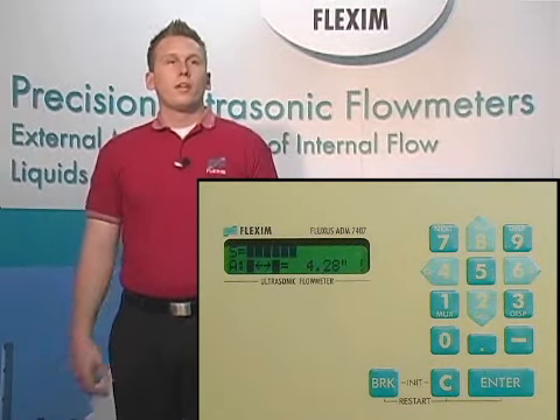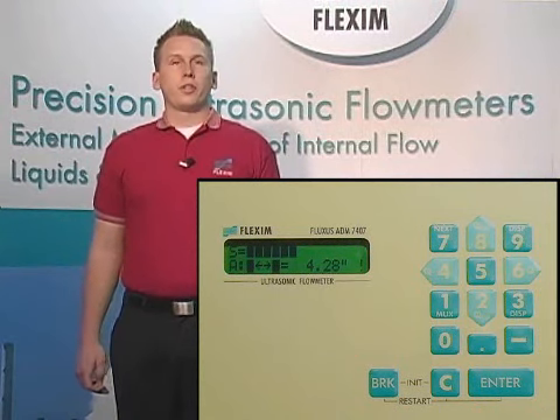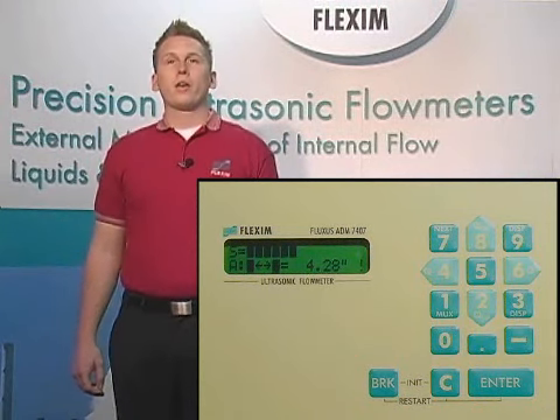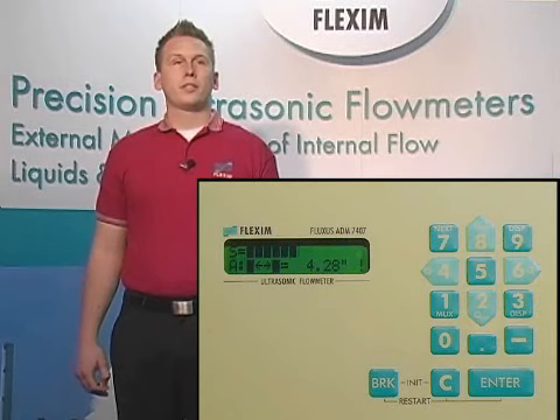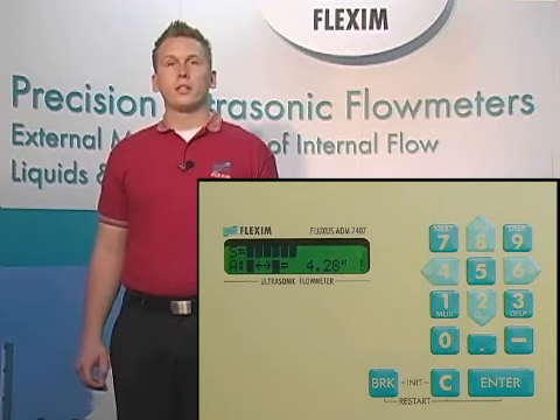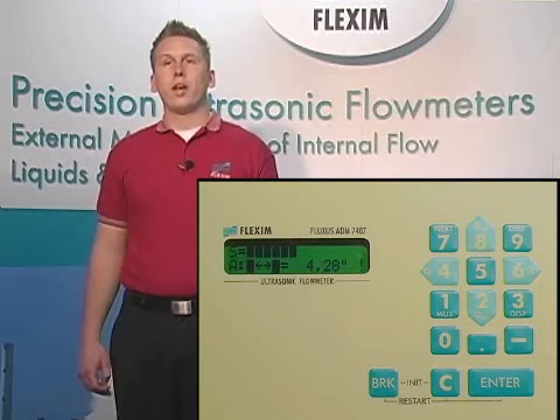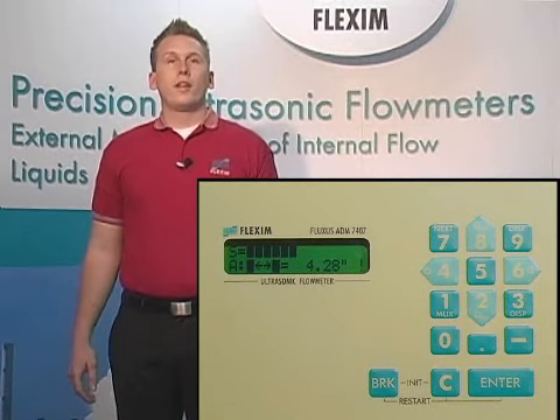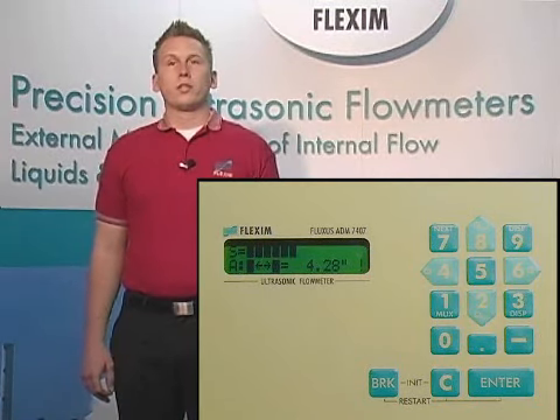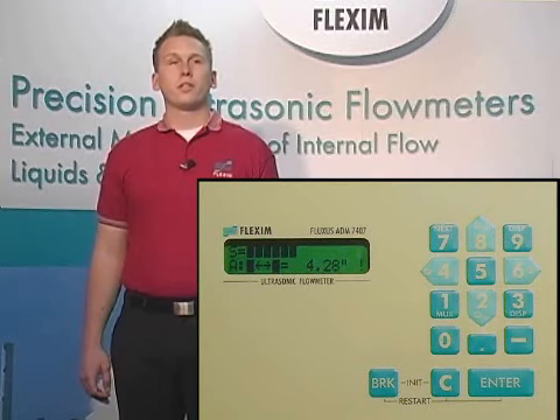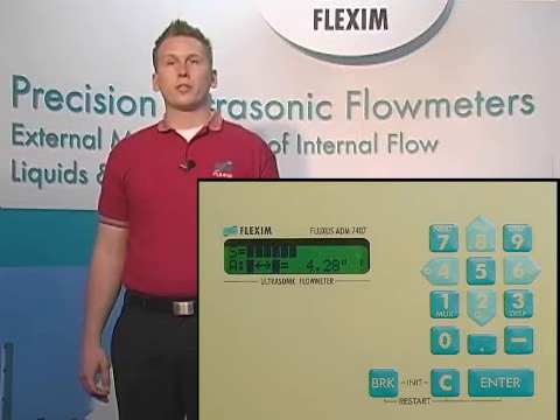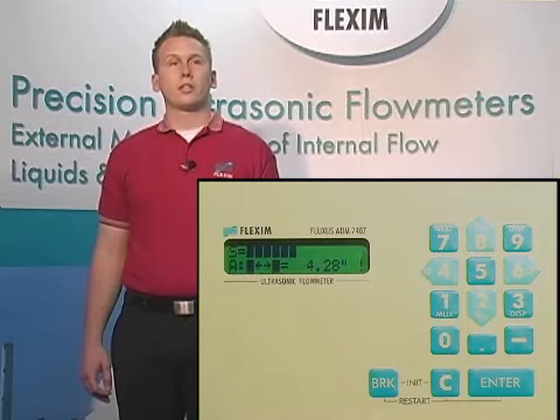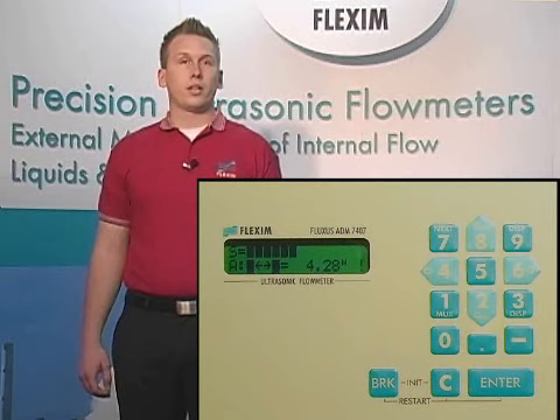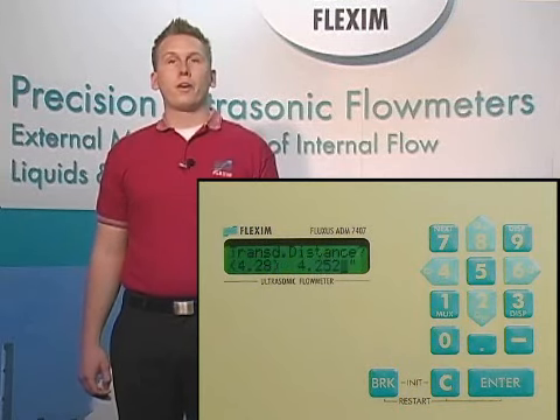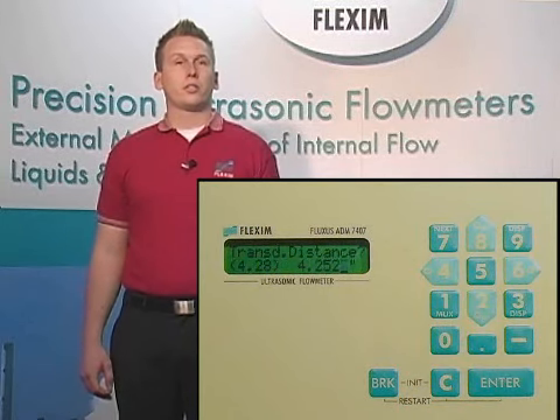This brings us to the signal quality screen. Here is where we actually mount our transducers on the pipe at a distance as close to the recommended distance and still easily found on a tape measure, as I've just described. Now, since we've already mounted our transducers, we'll need 2.5 to 3 bars of signal and a green light on the keypad. We have a green light, meaning we could start measuring, and 6 bars or 60% signal quality. This is a great signal. Let's hit enter now that we've verified we have a good signal and are ready to measure.